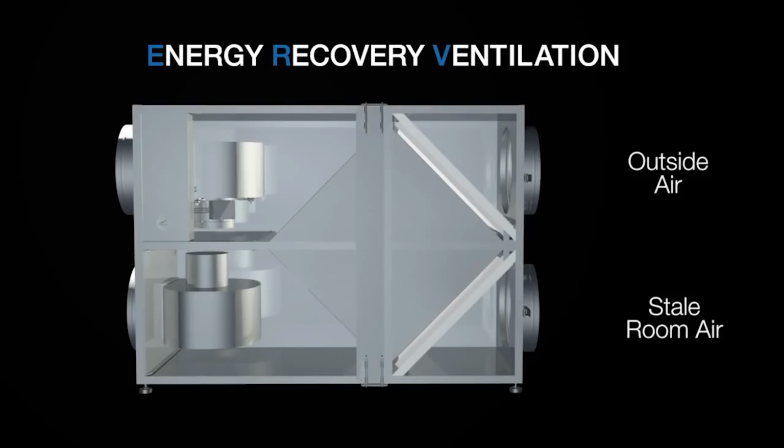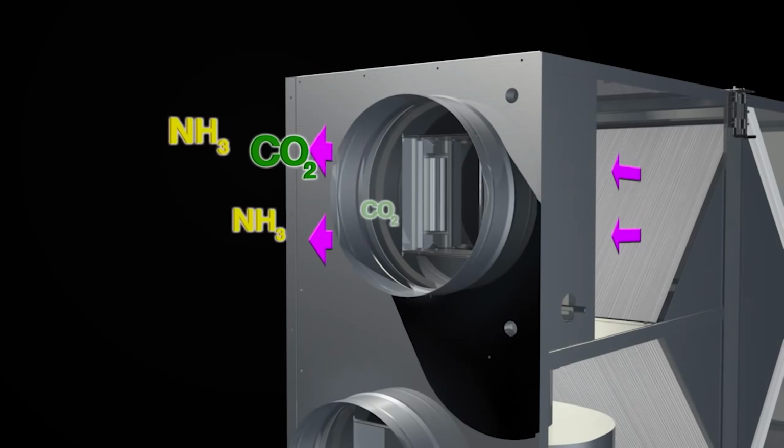We do what's called feed and bleed, where we bring a minimum amount of outside air into the building, and then we relieve a certain portion of that. Then we filter the air, that gets rid of the particulate. Then we heat the air and/or cool the air for personal comfort. And then we can humidify the air to increase the relative humidity within an operable range so we don't have static electricity problems and things like that.